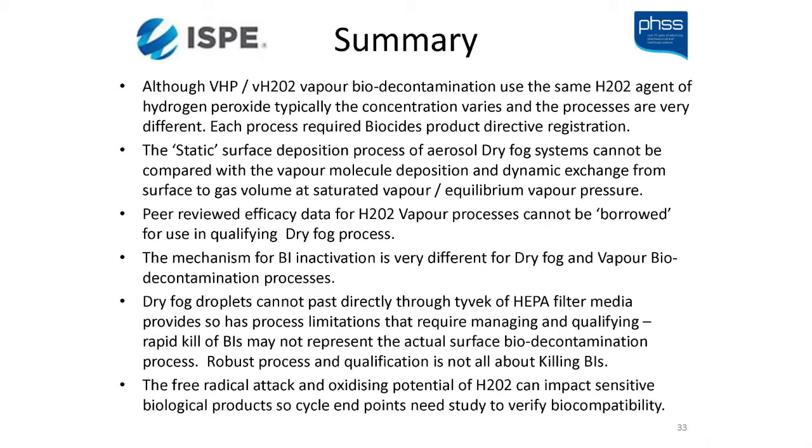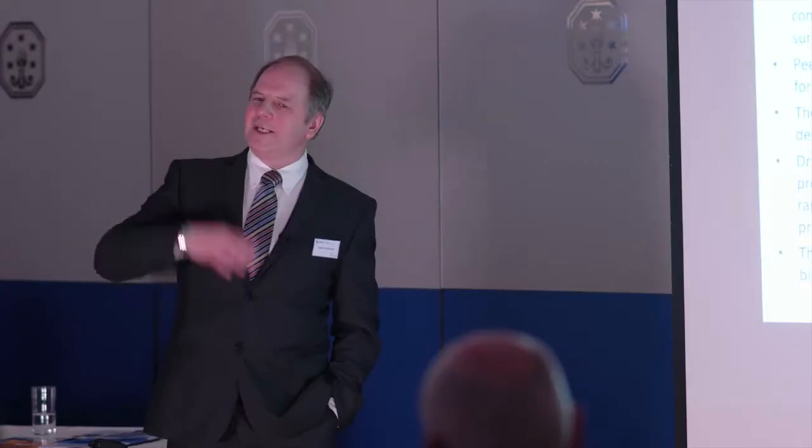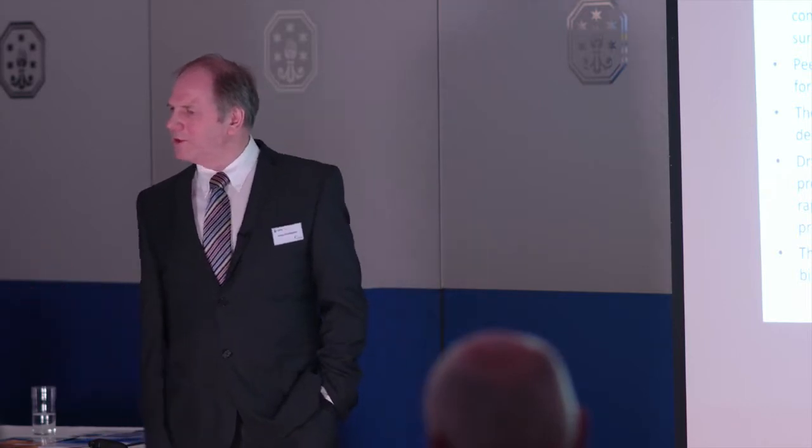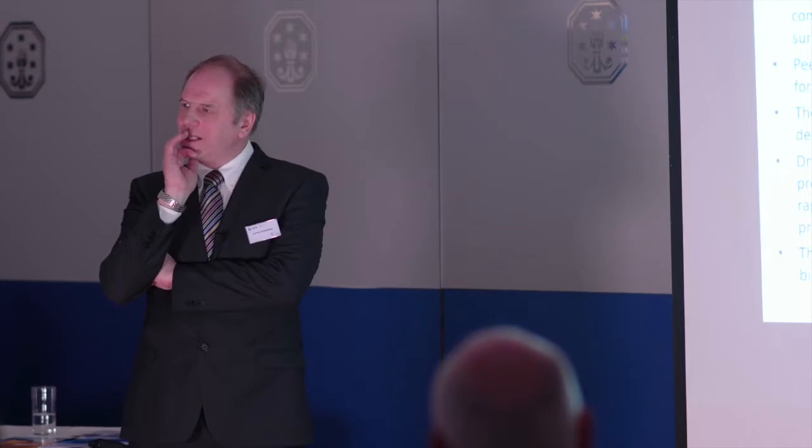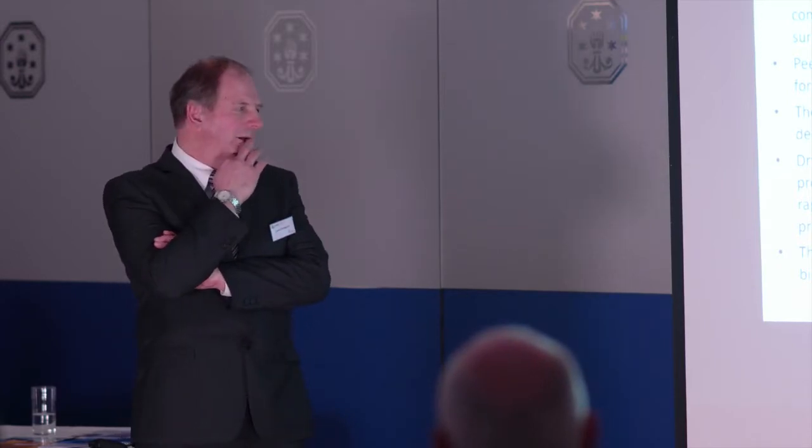So we're not going to get rid of biological indicators because we're always going to have those as the reference and correlate these new instruments to. But when we've built up the correlation data and we've seen it scalable, then there's an opportunity here. First, to use it as a tool to speed up validation alongside biological indicators, and in years to come, maybe, who's to say, maybe replacing. But for the time being, it's just about getting correlation and bringing it alongside.